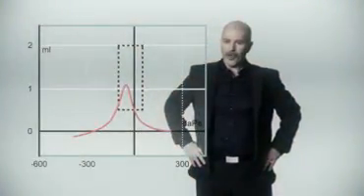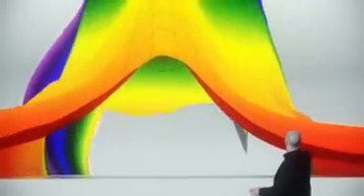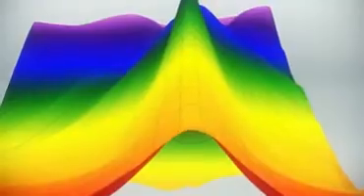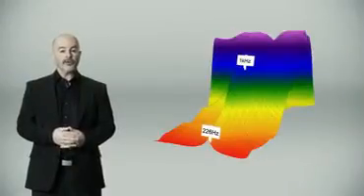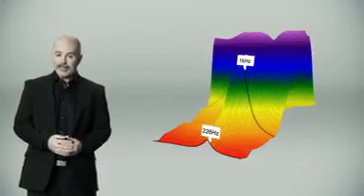This is what we work with today. This is what we will work with in the future: a mountain of data. Wideband tympanometry measures all tympanograms from 226 Hz to 8 kHz in a single fast pressure sweep, using the same procedure as classic tympanometry.